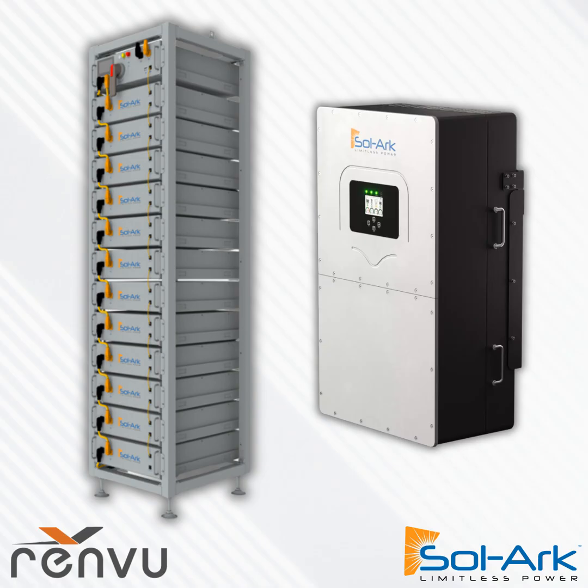But for large systems, you are buying multiple inverters and combining them together on a panel board. I would look at what's the maximum load of the facility and pick as many inverters as meets that maximum load, then add one more inverter for good measure, as far as what's the right size for whole building backup.